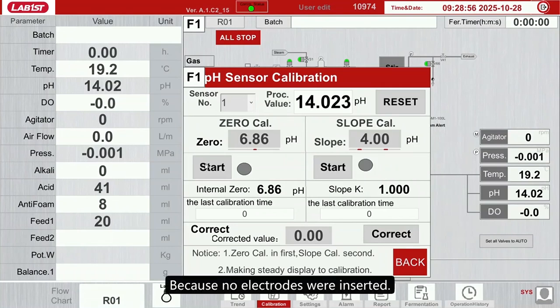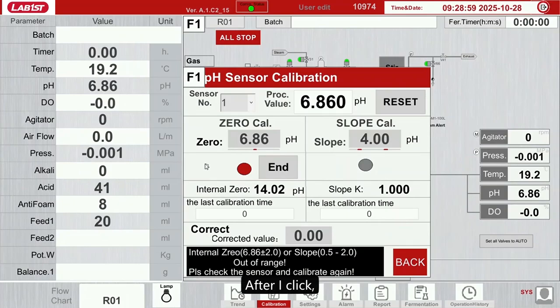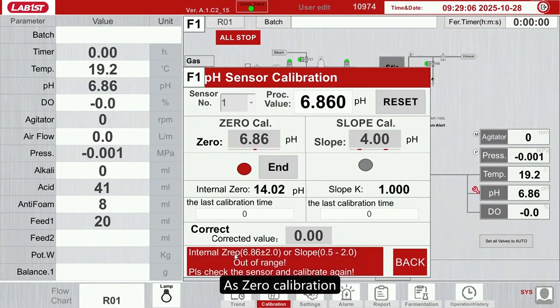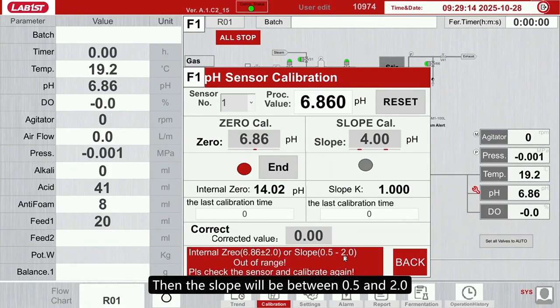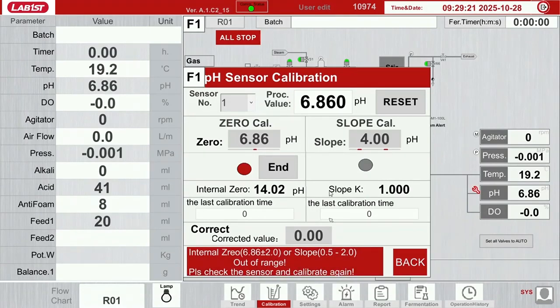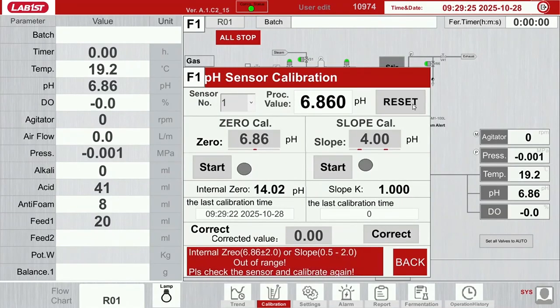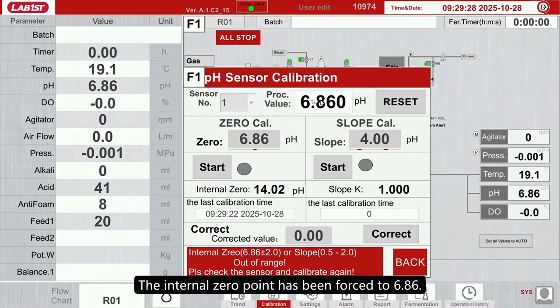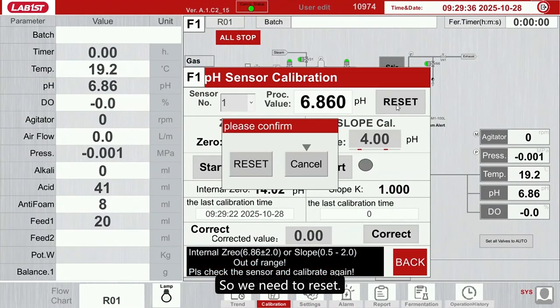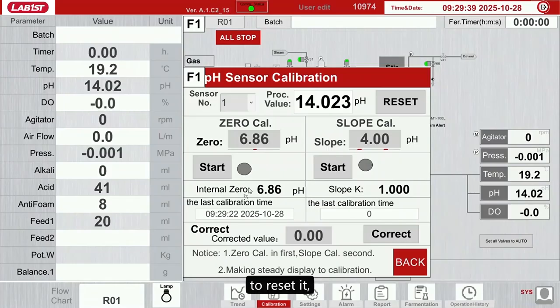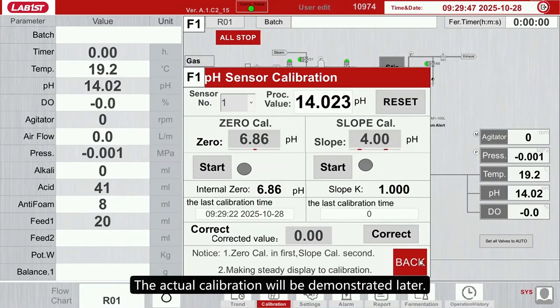Because no electrodes were inserted, I can demonstrate. After I click, because the deviation is too high, a prompt will appear here, as zero calibration is to be within plus or minus 2.0. Then the slope will be between 0.5 and 2.0. It has exceeded the range, so it alerts me that this calibration is abnormal. I need to recalibrate it. Then, as you can see after I click End, the internal 0 point has been forced to 6.86. This is already abnormal, so we need to reset it, and then recalibrate it. The actual calibration will be demonstrated later.